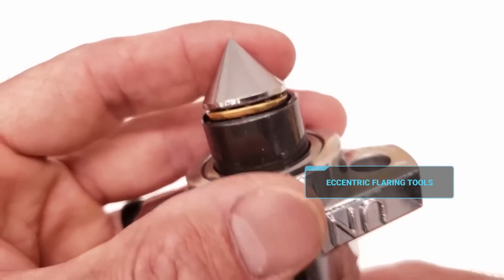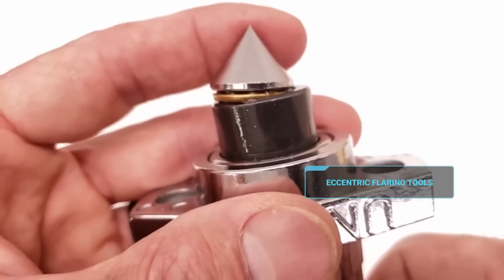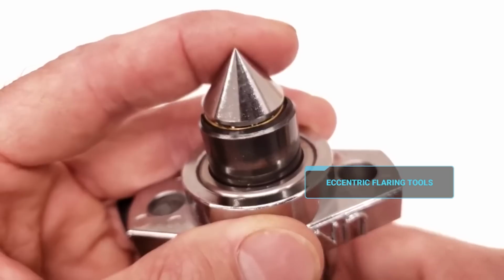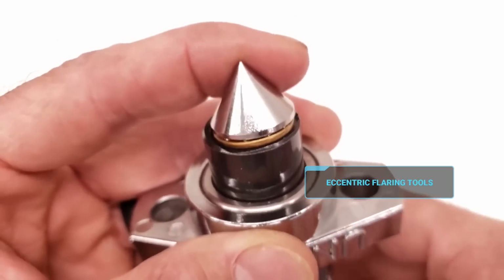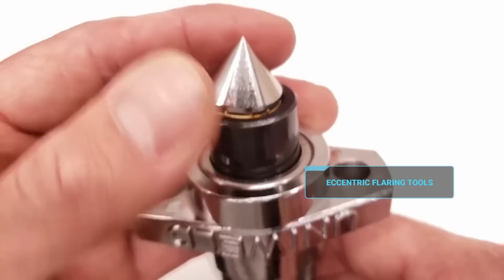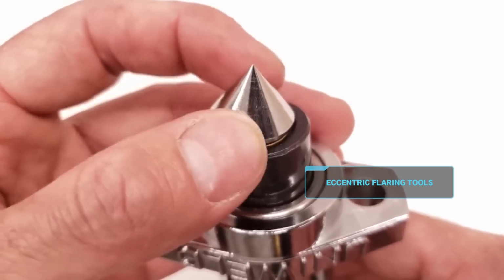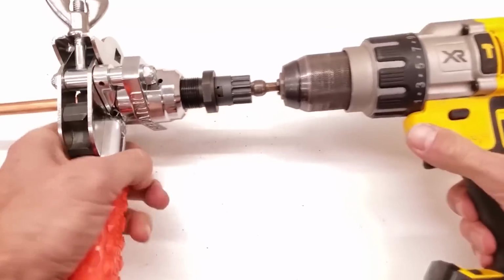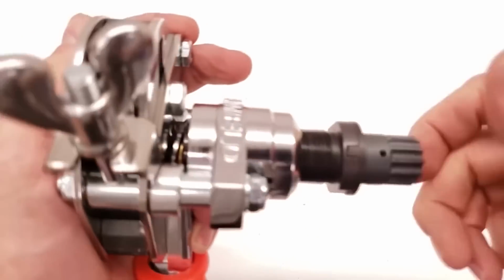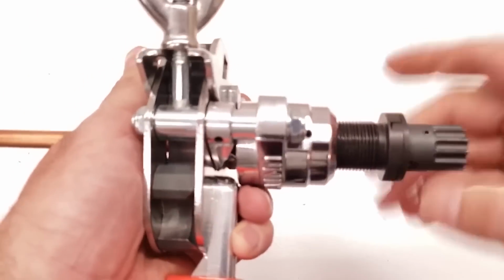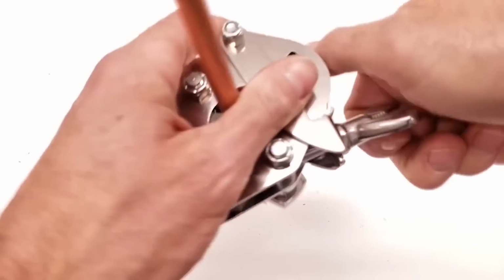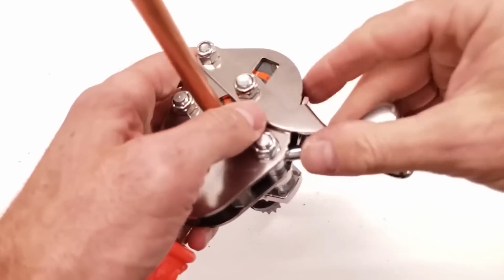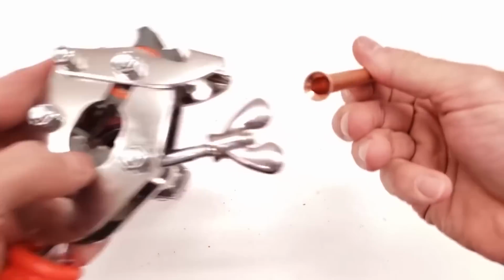I really like eccentric flaring tools, ones that have an offset cone so that when it's drawing out the flare, it's not pressing on the entire tube the whole time, so it produces less friction. It's easier to turn, especially if you have a manual one. You know, there's plenty of battery-operated electrical ones and ones that you can attach a drill to do your flaring process faster, and that's absolutely fantastic. And they have a depth guide, and so you can just set them right in there and keep making flare after flare after flare. It's a lot different than when, say, I came into the trade and just using a standard flaring block.